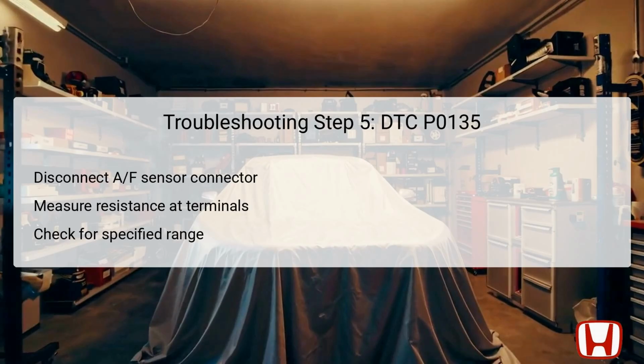Using a multimeter, the technician will measure the resistance between terminals number 3 and number 4. The expected resistance reading at room temperature should be within the range of 2.0 to 2.7 ohms. This measurement is crucial as it indicates whether the heater circuit is functioning within specified limits.